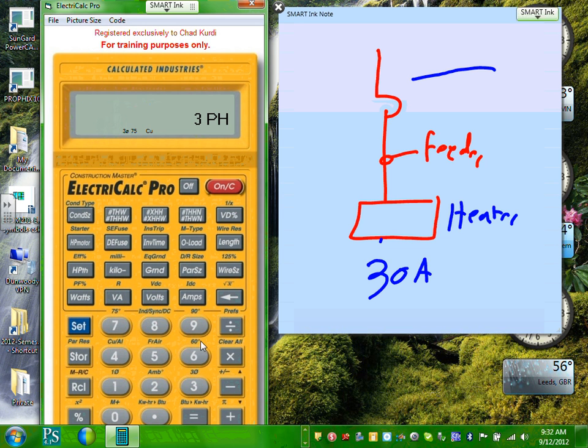Continuous load. Look what you do. Hit 30 and hit amps. Right? Everybody 30 amps. Now, since it's continuous load, you're going to do one step different. You're going to hit set. See what it says here, set. And hit the wire. It will size it based on 125% of that number. Can I have thumbs up, chat? It sizes it based on 125% of that number.